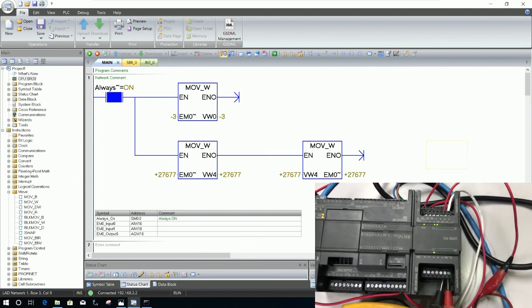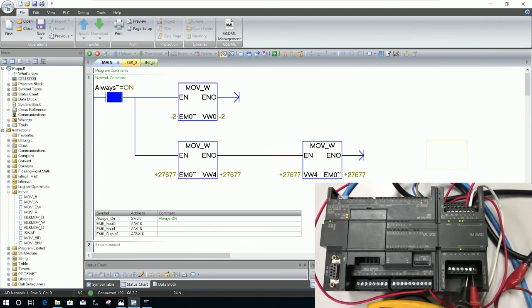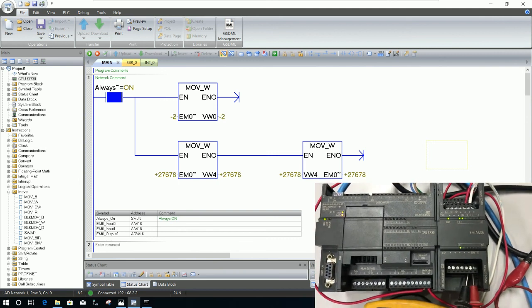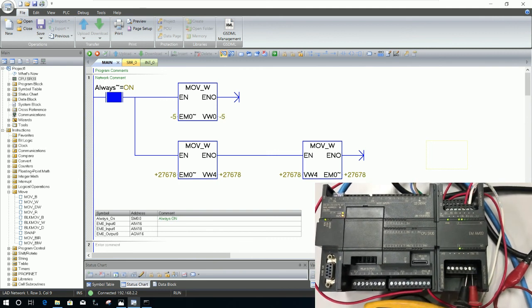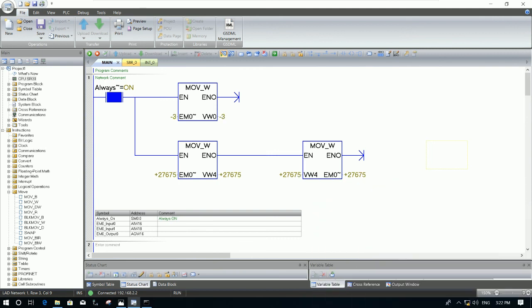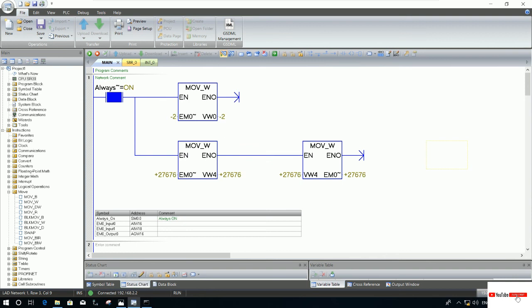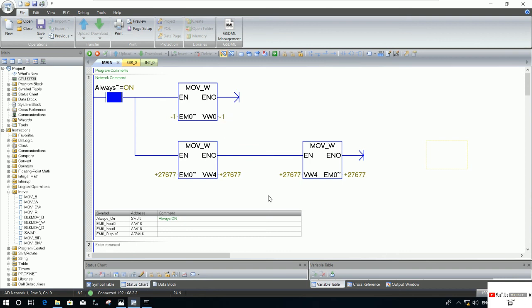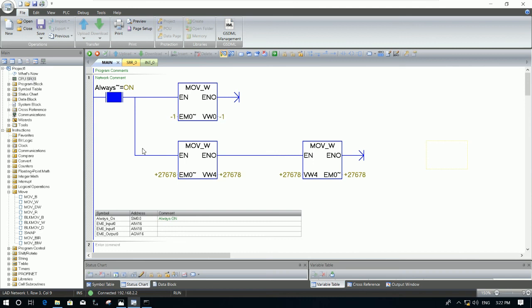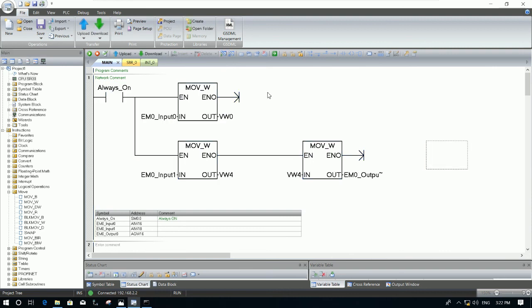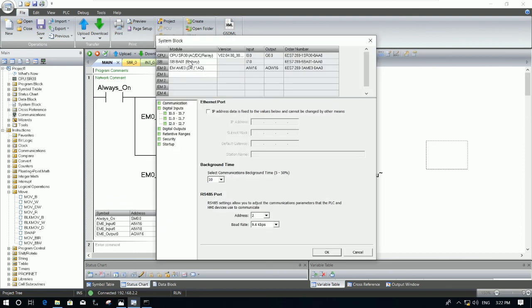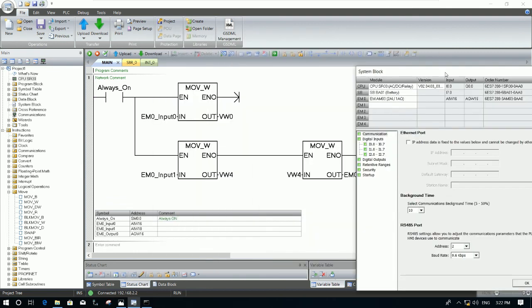So this is how to test the analog output module of PLC S7-200 Smart. For S7-200 we don't need to add a module, it's generated automatically, but for this S7-200 Smart we must config the module, otherwise it won't work.